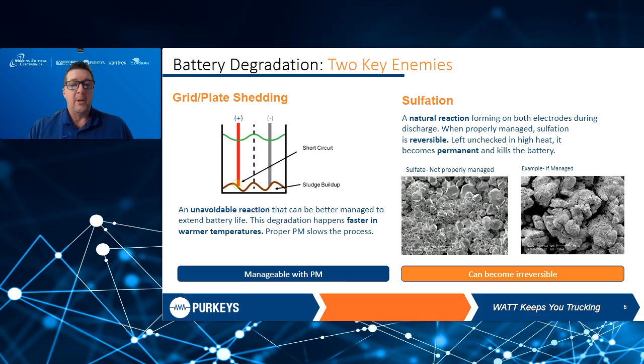One of the main components to sulfation happening is when you keep a battery below 12.4. When it's below that rate for an extended period of time, sulfation is going to happen in the battery. Also, extreme cold and extreme heat will cause that sulfation, but you also get grid plate shedding that happens faster during warmer temperatures. As you can see from the diagram on the left, some of that sludge sheds off of those plates and builds up at the bottom of the battery, and then of course it creates a short circuit, most likely at the time when you need it the most.